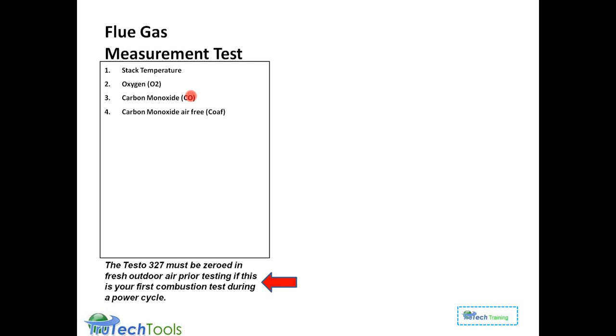And by the way, anything you pop up in your flue gas measuring display, you can change the order. This is the order that comes up as standard at my last check. But you can move the order around and place any of these parameters that you want in the screen in any order that you wish. Whatever you put on the screen is what will appear on the printout. So that's something to keep in mind. When you configure the screen location, you're configuring the printout list.